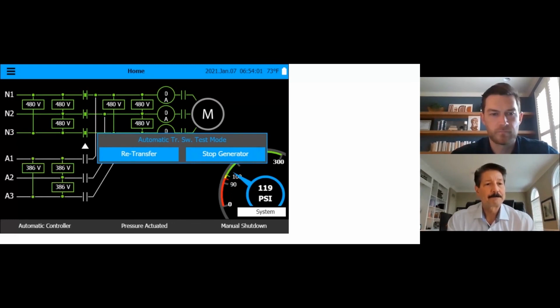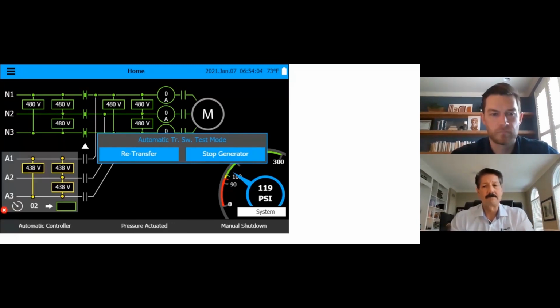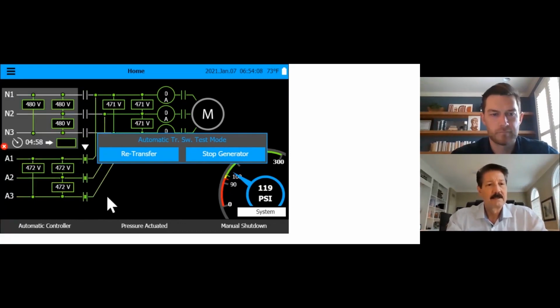So as you can see, we send a signal to the genset. It's ramping up, yellow's caution, it's still trying to retain it. And before the generator switches over, it needs to get up to 90% of nominal voltage, needs to be in sync at 60 hertz, and there must not be a phase reversal on the emergency power, otherwise it won't transfer over. In this case, it was successful. We have it energized. You see the arrow now points down, and should we have a pump on demand, it will be running off emergency power.